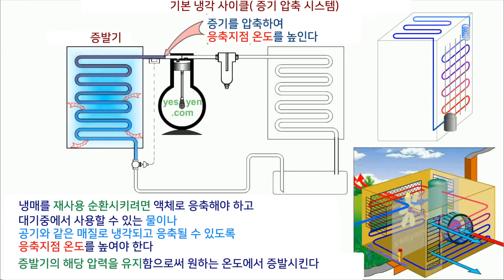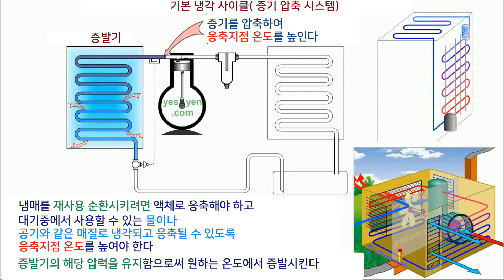To reuse the refrigerant, it has to be condensed to liquid state. For this, the condensing — that is, the boiling point temperature — has to be increased so that it can be cooled and condensed by a medium like water or air available at atmospheric temperature. Hence the vapor is compressed in a compressor to increase the pressure and the corresponding condensing, that is boiling point temperature.